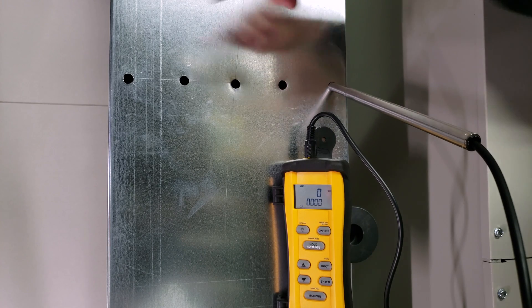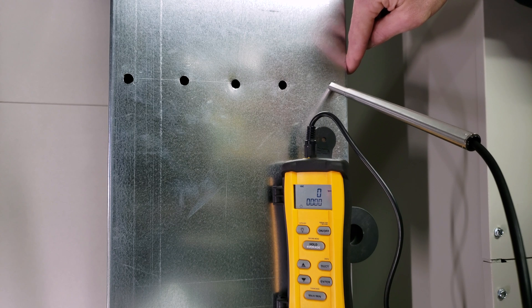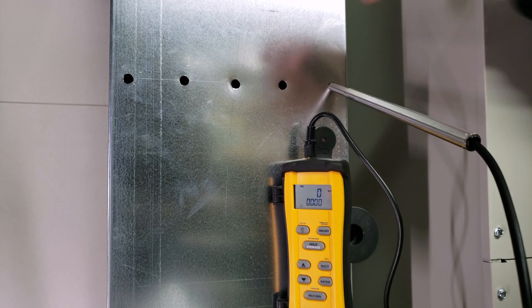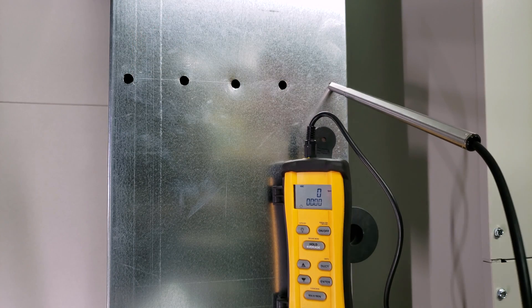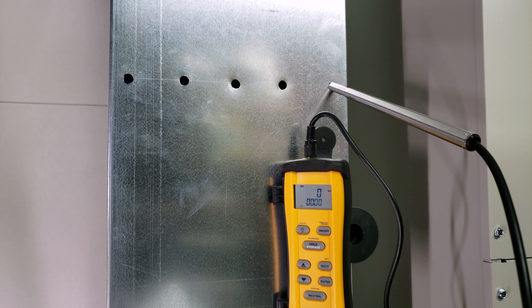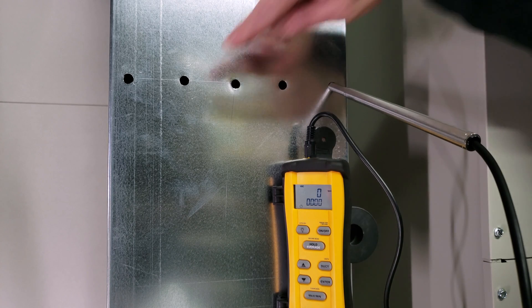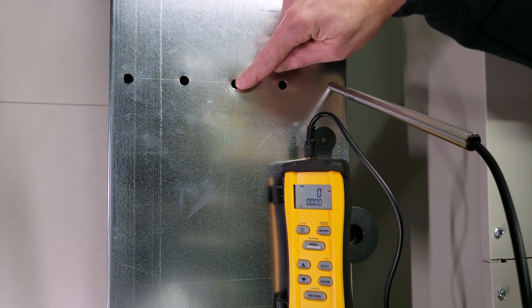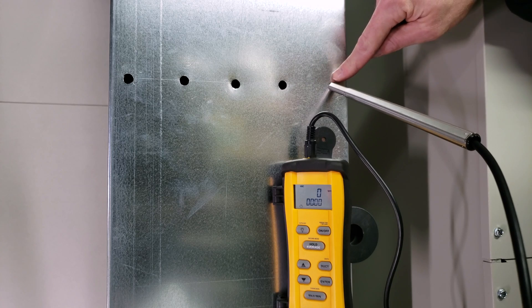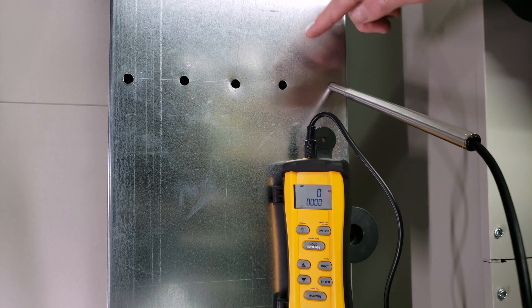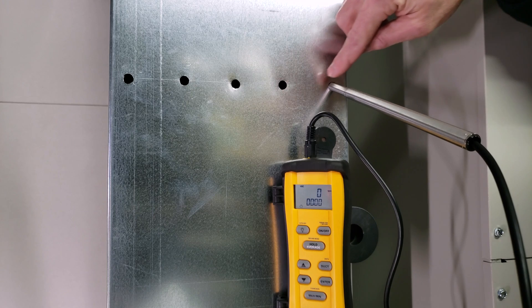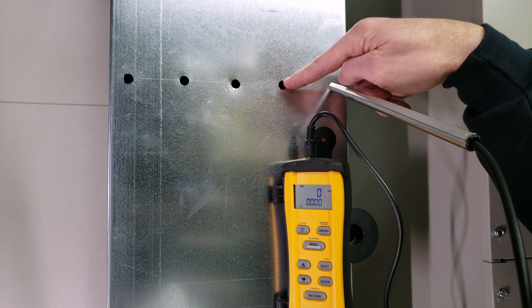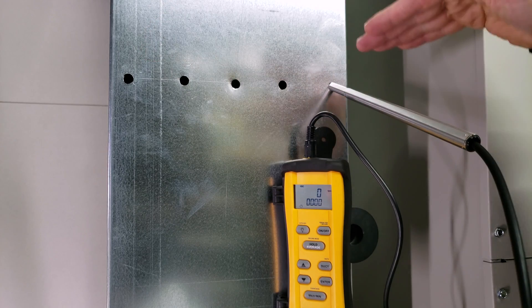For a 10.25 inch duct, take your calculator: 10.25 times 0.074 gives you around three-quarters of an inch. 10.25 times 0.288 gives you around three inches. 50% is right in the middle. The other side is a mirror image, so you don't have to calculate 71.2% and 92.6% separately. You know where all your holes are drilled.